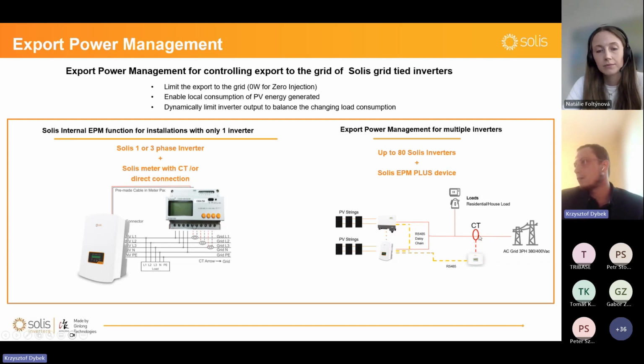The current transformers can be placed also in high voltage side of the transformer, but you need to change something inside the EPM. Soon this information will be released also in just a basic manual. So the point is just to change some settings inside, and it's all will be good. Of course, EPM itself needs to be connected on a low voltage side, because yeah, 11,000 volts, it's not recommended for this device. Let's say like this.